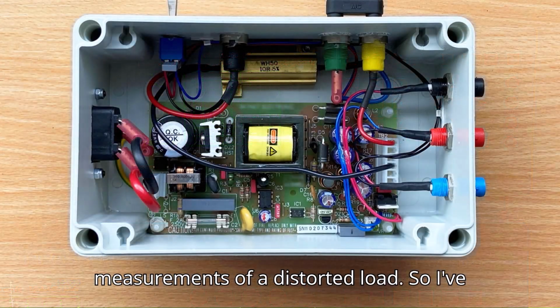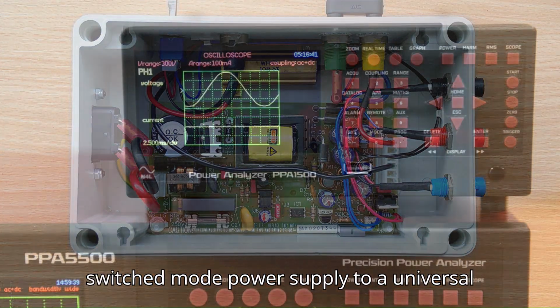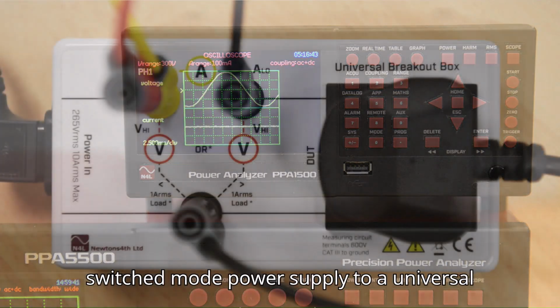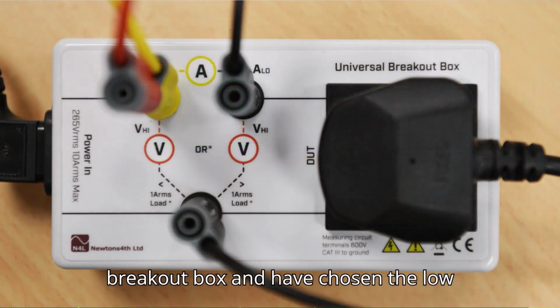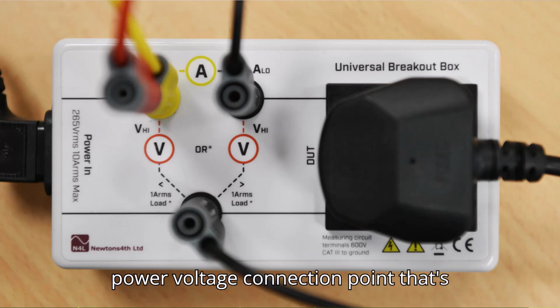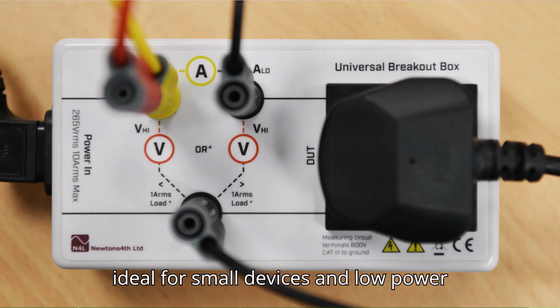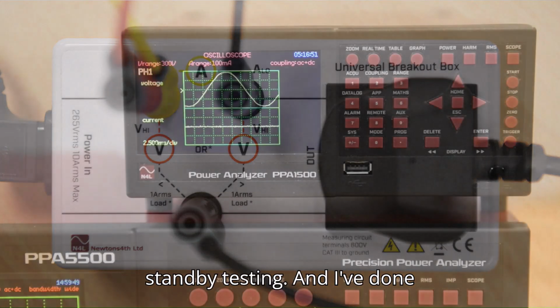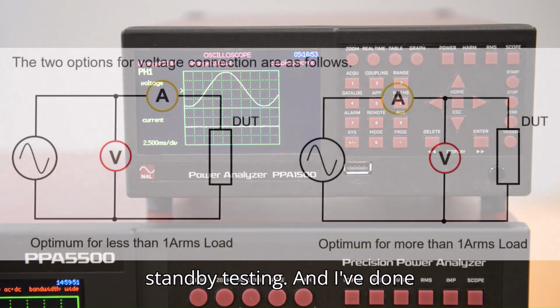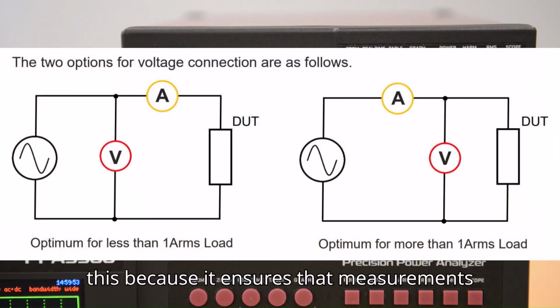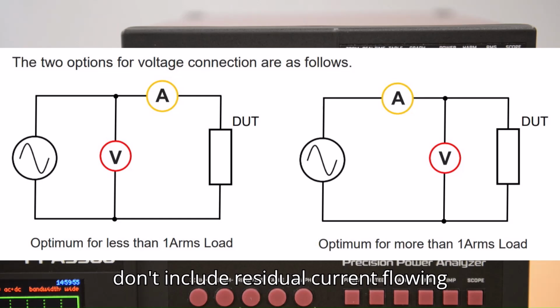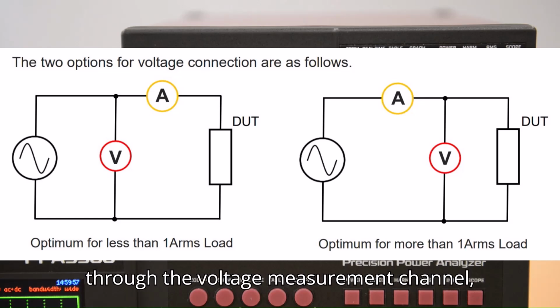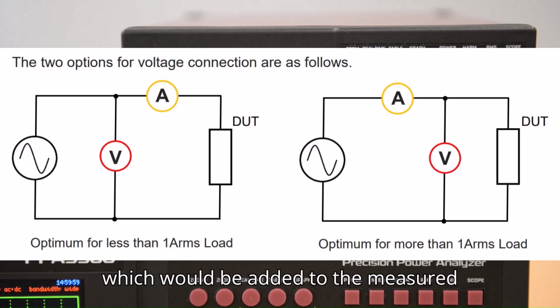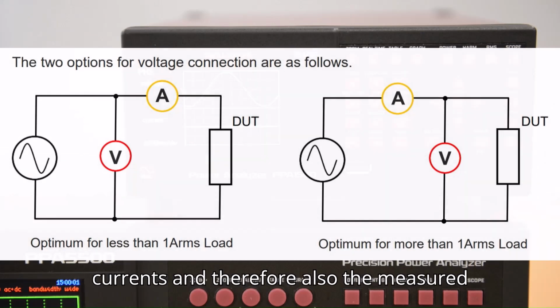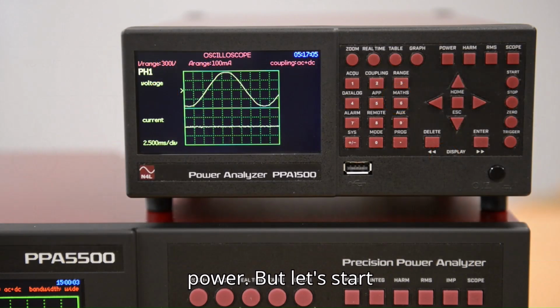So I've connected a commercially available switch mode power supply to a universal breakout box and have chosen the low power voltage connection point that's ideal for small devices and low power standby testing. And I've done this because it ensures that measurements don't include residual current flowing through the voltage measurement channel, which would be added to the measured current and therefore also the measured power.